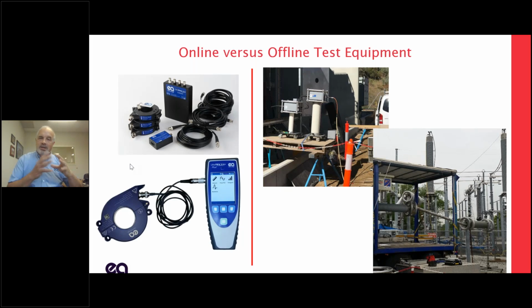A lot of people talk about online testing, offline testing. The obvious big problem with offline testing is that you have to take an outage. Take this cable, disconnect it, take it out of service, bring in test equipment, and you've got kind of two choices for test equipment. One is the VLF, or very low frequency, 0.1 hertz or 0.01 hertz, and that's what that picture in the middle is, some VLF test equipment. It's still pretty hefty. I need to re-energize this line to line voltage or higher.